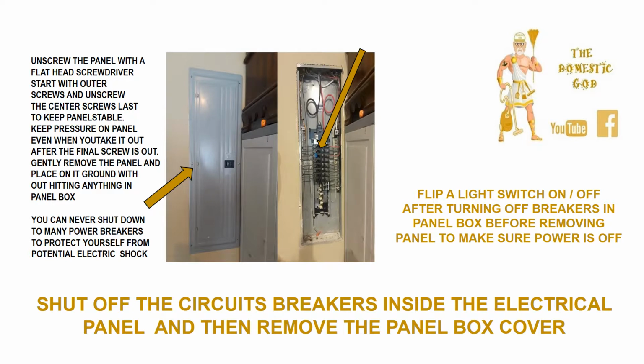After you have shut off the main breaker and the house breaker outside, come back in and shut off the circuit breakers inside the electrical panel, and then remove the panel cover from the box. Unscrew the panel with a flathead screwdriver. Start with the outer screws and unscrew the center screws last to keep the panel stable. Keep pressure on the panel even when you take it out after the final screw is out. Gently remove the panel and place it on the ground without hitting anything in the panel box.